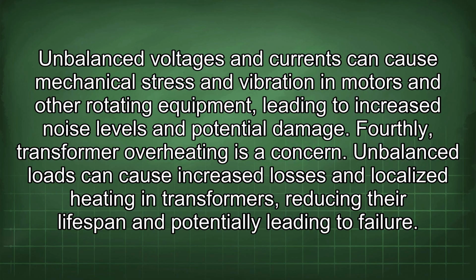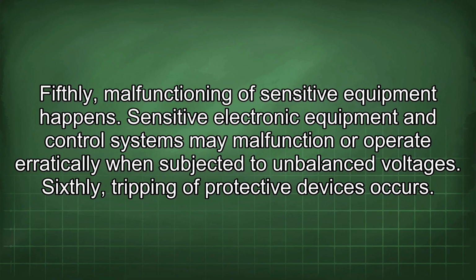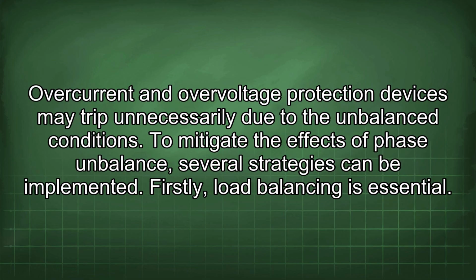Fourthly, transformer overheating is a concern. Unbalanced loads can cause increased losses and localized heating in transformers, reducing their lifespan and potentially leading to failure. Fifthly, malfunctioning of sensitive equipment happens. Sensitive electronic equipment and control systems may malfunction or operate erratically when subjected to imbalanced voltages. Sixthly, tripping of protective devices occurs. Overcurrent and overvoltage protection devices may trip unnecessarily due to the unbalanced conditions.